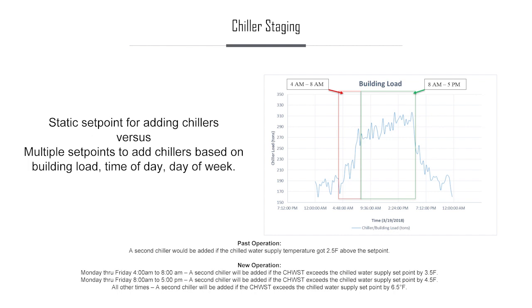Jason, in particular, said, well, wait a minute here. Did we ever really need that second chiller to come on? Because by the time it might be sensed as uncomfortable in the building, everybody was walking out the door anyway at end of day. Could we put in some logic to delay the need for that second chiller to come on? So a three-step logic was just written into the code there.